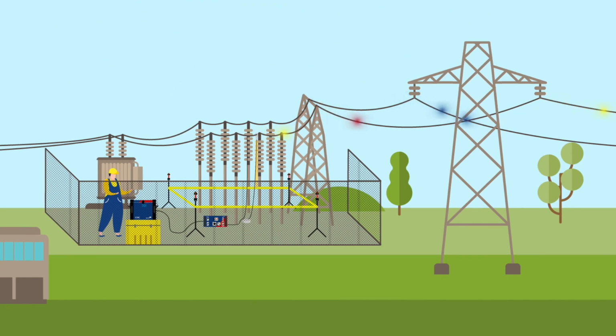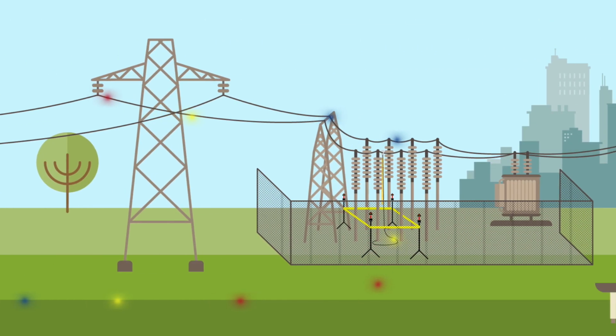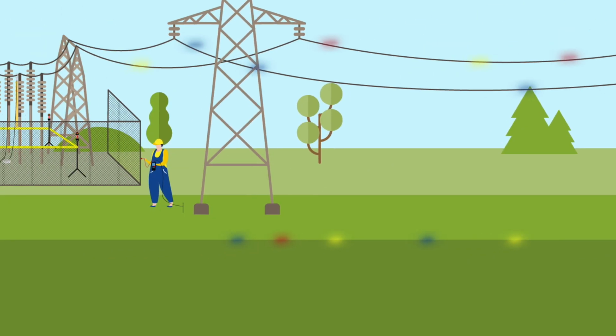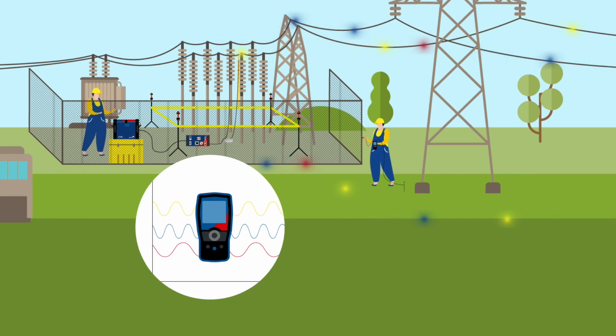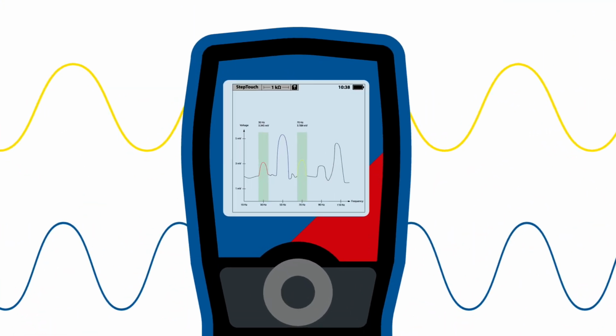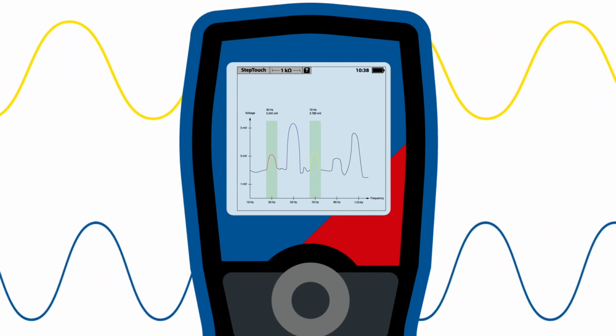The CPC 100 uses the so-called Frequency Selective Method to inject a test current into the grounding system. Frequency selected measurements are performed on the resulting voltages and currents to reliably suppress interference and disturbance voltages. This provides very reliable results. The test current can be injected in two different ways. The power line injection uses a disconnected power line to inject the test current via remote grounding system. The current probe injection uses an auxiliary current probe to inject the test current.